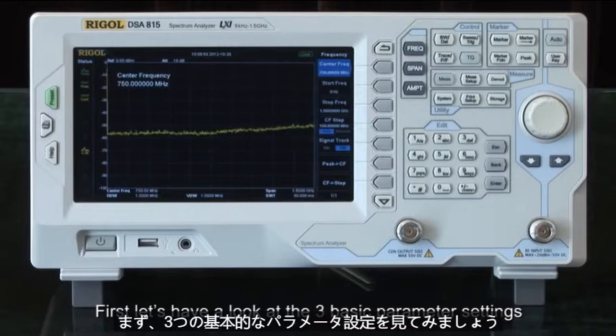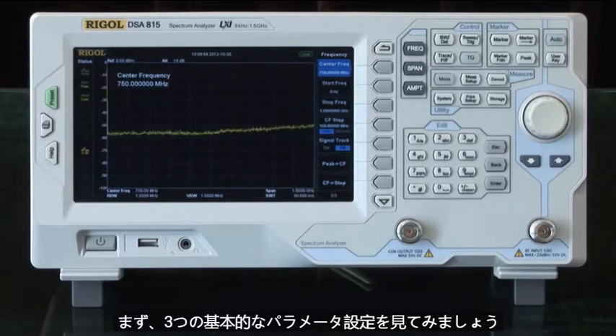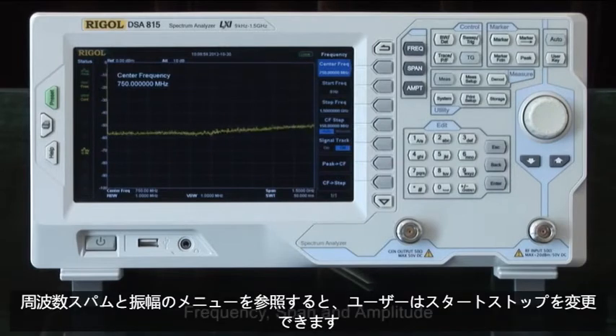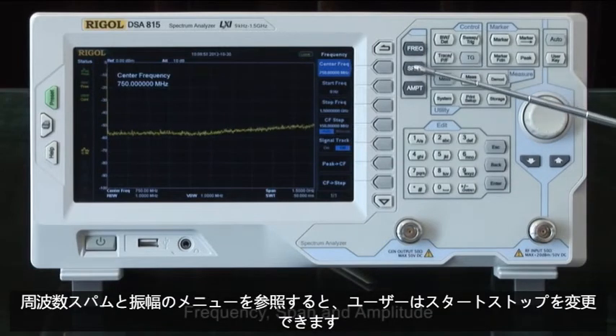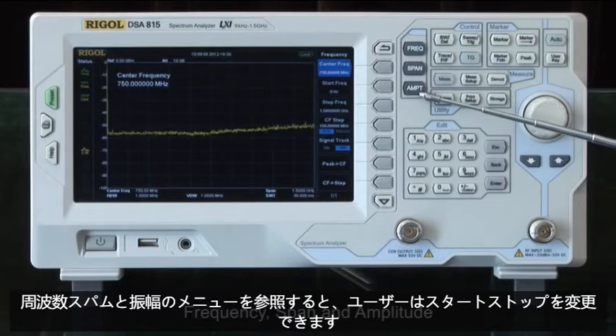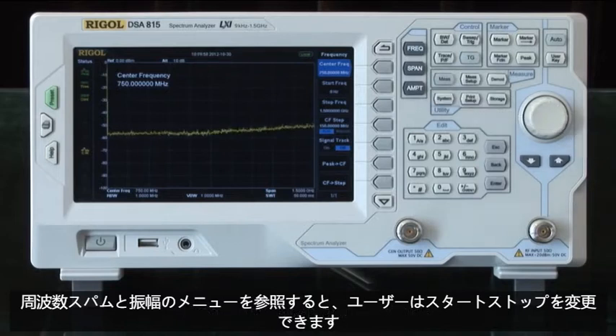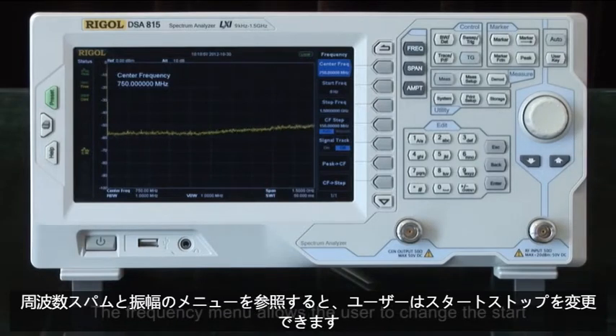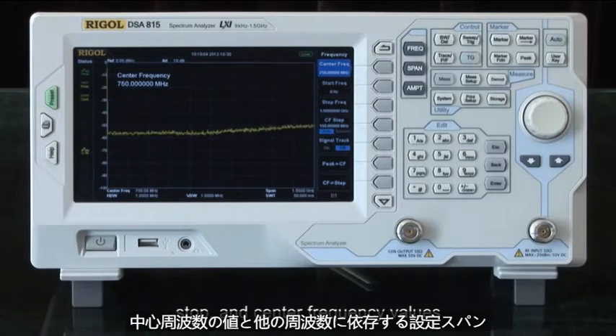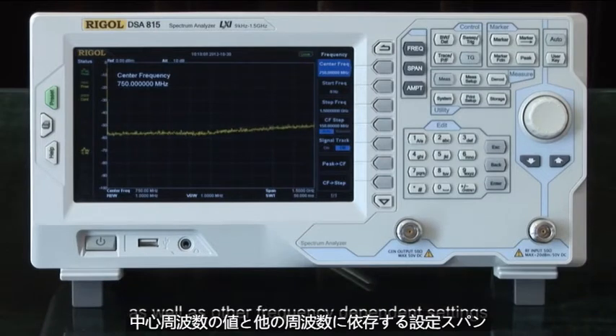First, let's look at the three basic parameter settings of frequency, span, and amplitude. The frequency menu allows the user to change the start, stop, and center frequency values as well as other frequency-dependent settings.